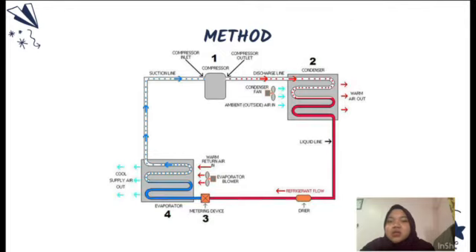The next one is the metering device, which is the expansion device. It is used to divide the point between the high pressure and low pressure sides of the system. It is also designed to maintain a specific flow rate into the low side of the system, to avoid any incorrect quantity of refrigerant flowing into the evaporator.